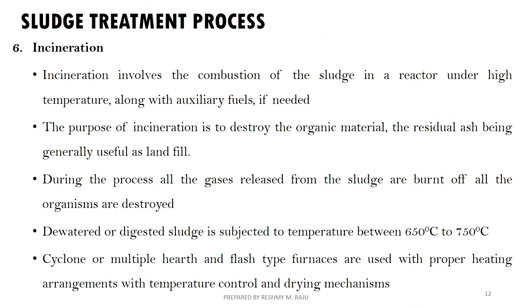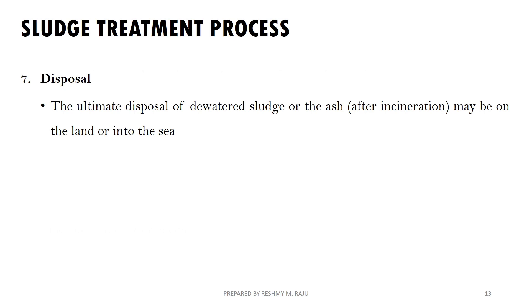When air pollution control mechanisms are used, we will use soil conditioners like granules. We will use auxiliary fuels. When we mix the sludge at high temperature, any organic materials undergo incineration. The ash is disposed of in a landfill. Any pathogenic organisms are fully destroyed in this process at 650 to 750 degrees. Equipment includes cyclones and multiple hearth furnaces.